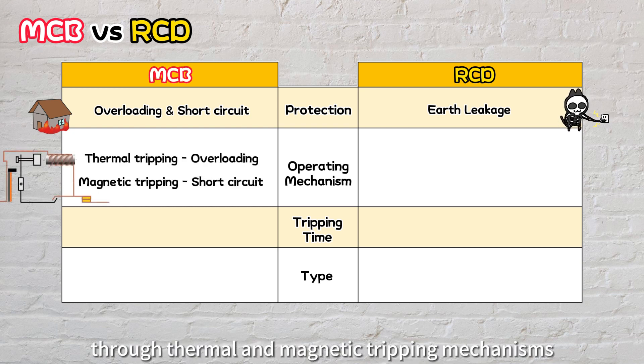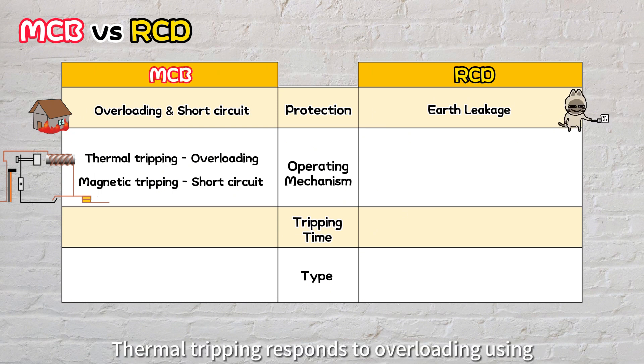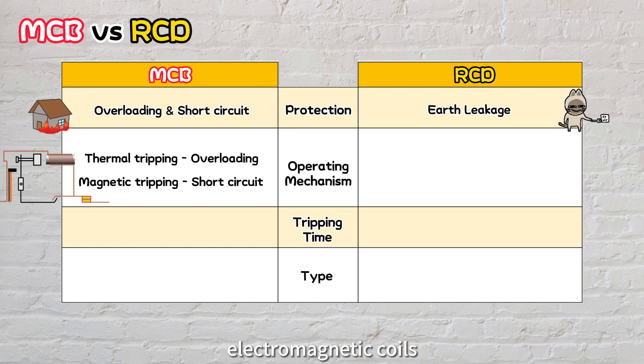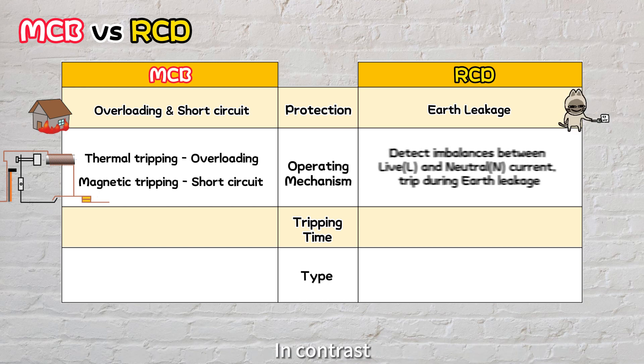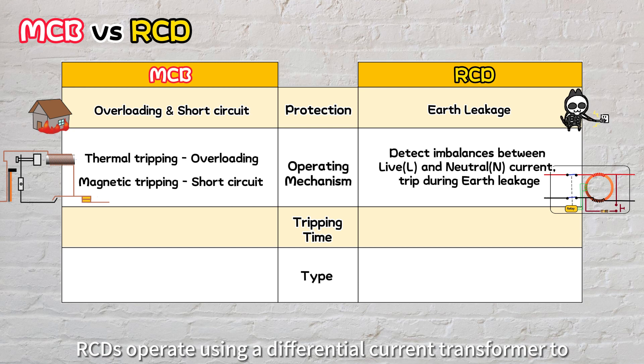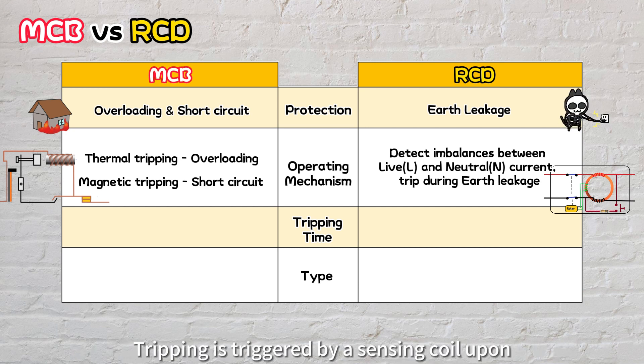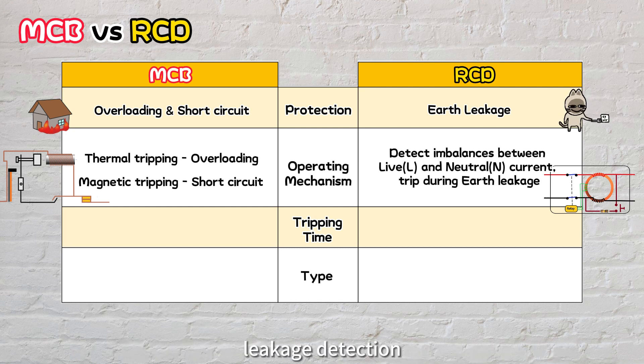MCBs function through thermal and magnetic tripping mechanisms. Thermal tripping responds to overloading using bimetallic strips, while magnetic tripping reacts to short circuits through electromagnetic coils. In contrast, RCDs operate using a differential current transformer to detect imbalances between the live and neutral currents. Tripping is triggered by a sensing coil upon leakage detection.